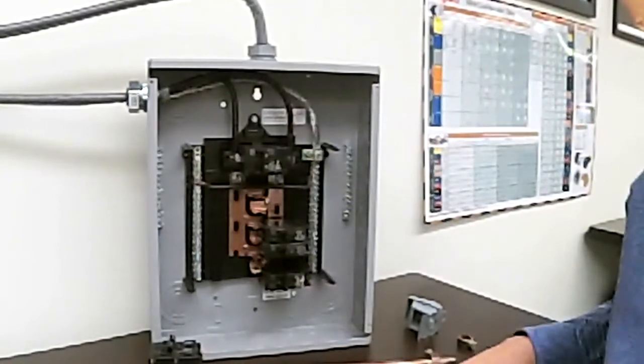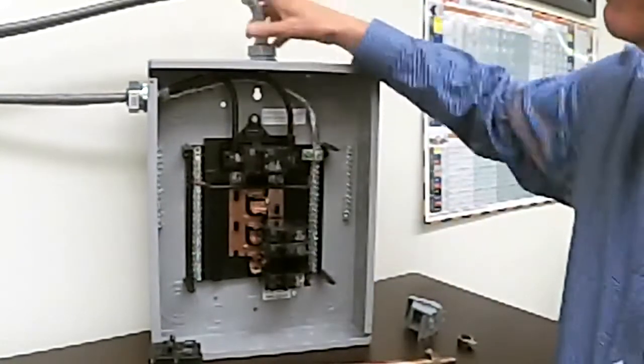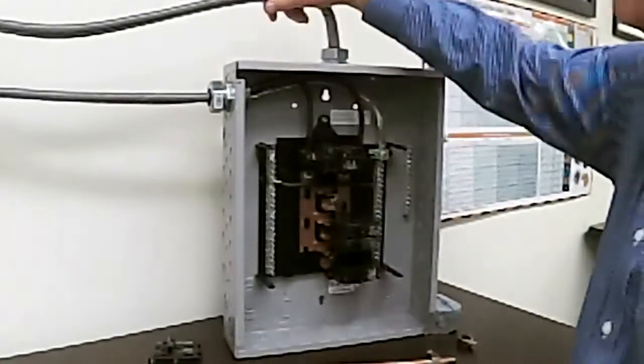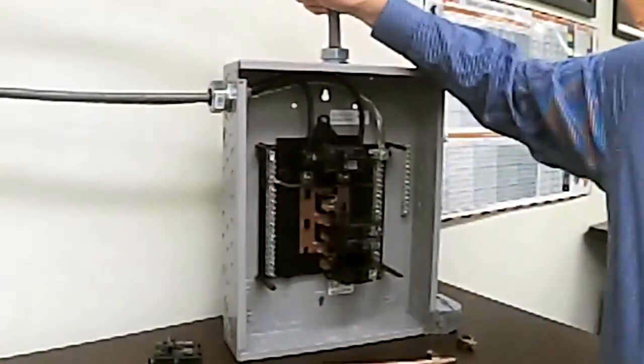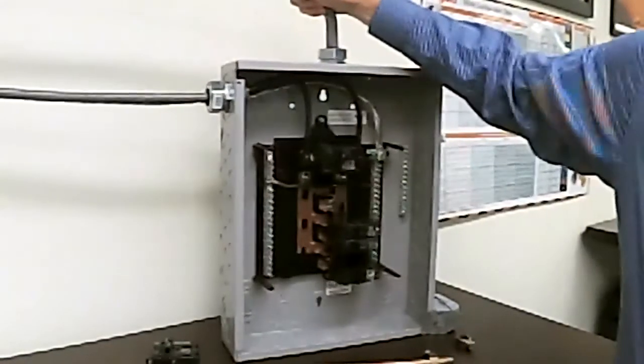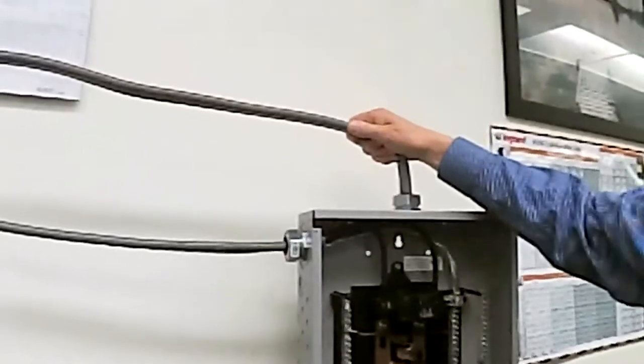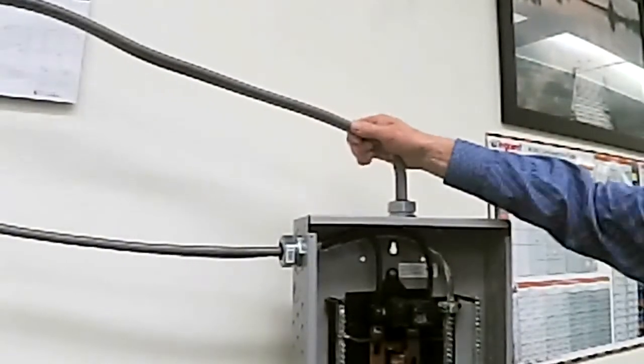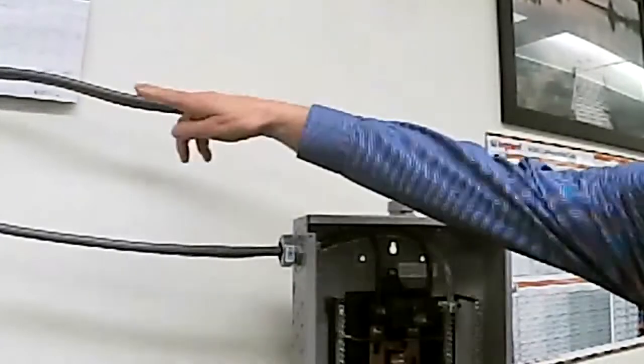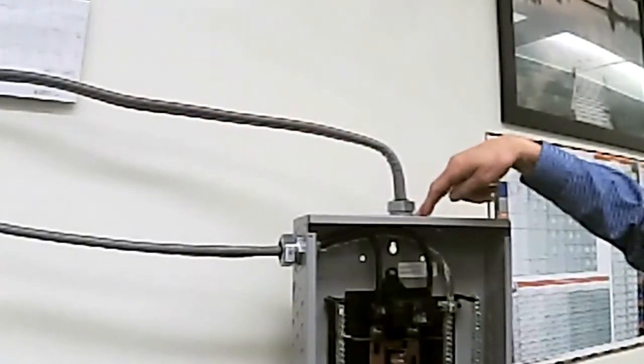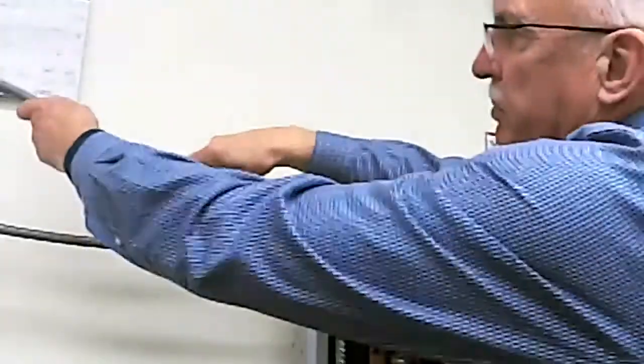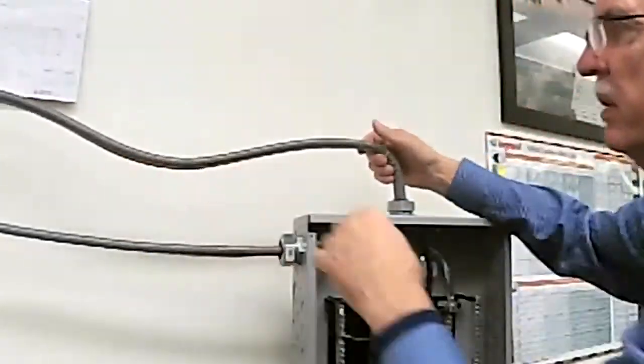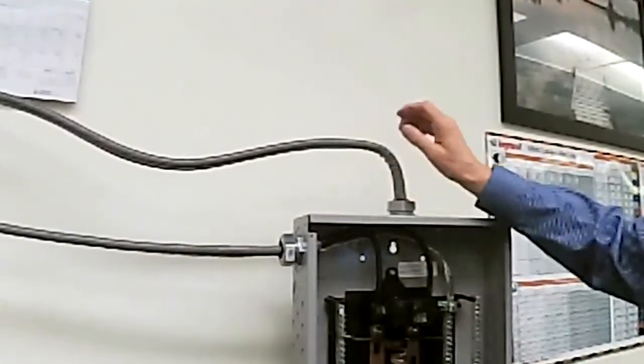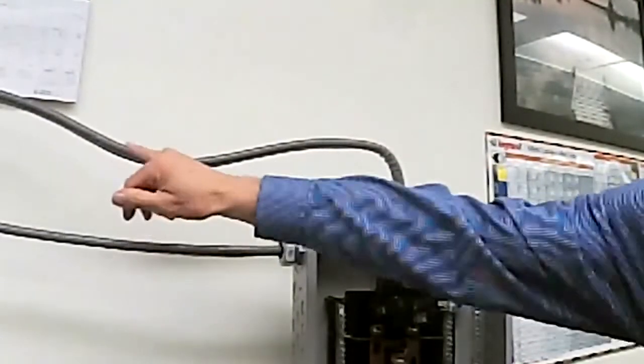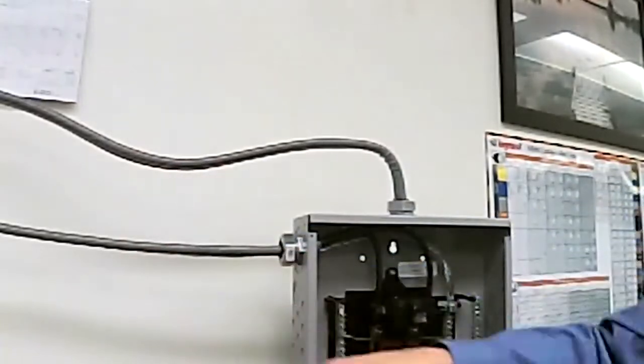If you have questions, go ahead and send them in. The other thing is, I want to mention this. If this is your circuit breaker panel, again, don't come in diagonally, straight down into a panel like this. All you're doing is giving a nice runway for water to enter the panel. Make some type of a bend, like that, which will give a place for any condensation or outside water to drip off outside of the panel.